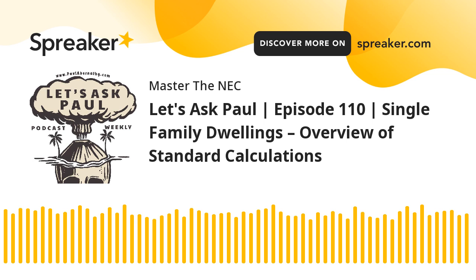And the conductors that we're talking about are seeing 100% of the load, right? That means we don't have a meter feeding a panel outside with a couple breakers in it, and then going from the load side of that inside, feeding another panel, so that the conductors from that outside panel to the inside panel are not seeing 100% of the load. You with me? Or even if we had a service disconnecting means outside, and everything on the load side of that would be a feeder, let's say, it's still seeing 100% of the load because all that is a disconnect outside. This can get confusing for people. So let me make it simple. As long as the conductors in question are seeing 100% of the load that can be applied, then you can apply these rules.